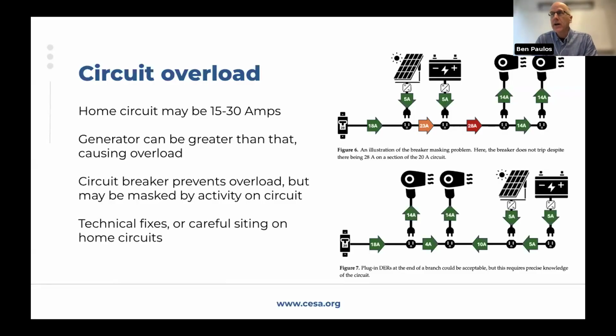UL's job is to assume the worst, so I will give them that. These diagrams show a case: the top diagram shows a case where, let's say you have a 20 amp circuit and you decide to plug in two hair dryers at the same time. Each of them draws 14 amps, so you're drawing 28 amps on a 20 amp circuit. That's the red arrow here. That line would overheat and potentially cause a fire. And to prevent it, the circuit flips and shuts off the power.